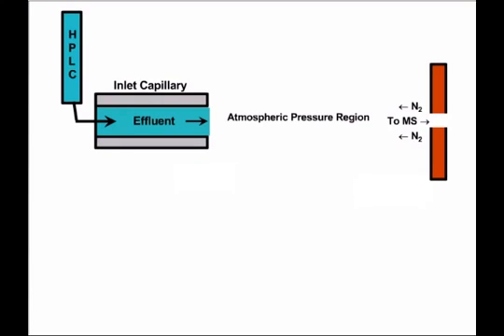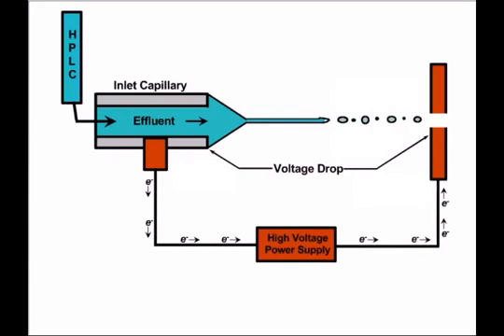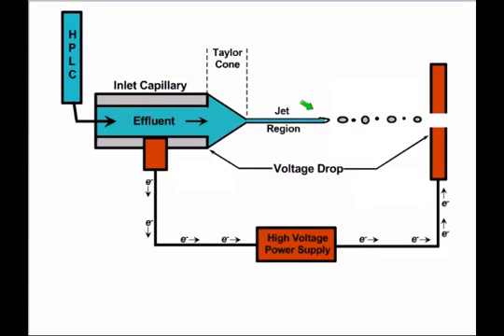What actually makes this an electrospray interface, however, is the presence of a high voltage power supply which has been applied from the inlet capillary to the inlet to the mass spectrometer across this atmospheric pressure region. When we apply high voltage to a capillary which is carrying a liquid flow, we get this characteristic formation of what's known as a Taylor cone. The Taylor cone is pulled into a jet, and that jet is further disrupted into a series of droplets. This is again very characteristic of applying a high voltage to this inlet capillary.